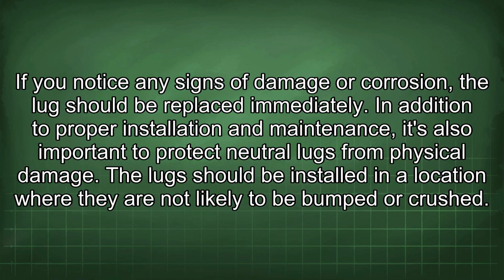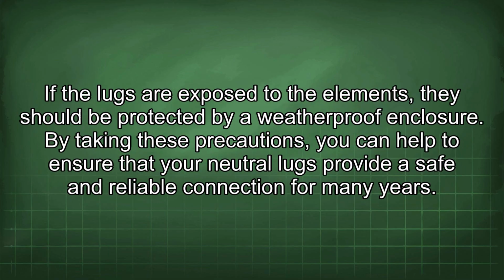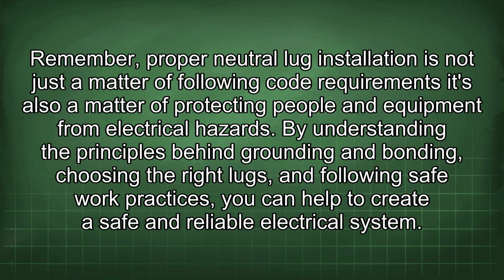In addition to proper installation and maintenance, it's also important to protect neutral lugs from physical damage. The lugs should be installed in a location where they are not likely to be bumped or crushed. If the lugs are exposed to the elements, they should be protected by a weatherproof enclosure. By taking these precautions, you can help to ensure that your neutral lugs provide a safe and reliable connection for many years. Remember, proper neutral lug installation is not just a matter of following code requirements, it's also a matter of protecting people and equipment from electrical hazards. By understanding the principles behind grounding and bonding, choosing the right lugs, and following safe work practices, you can help to create a safe and reliable electrical system.